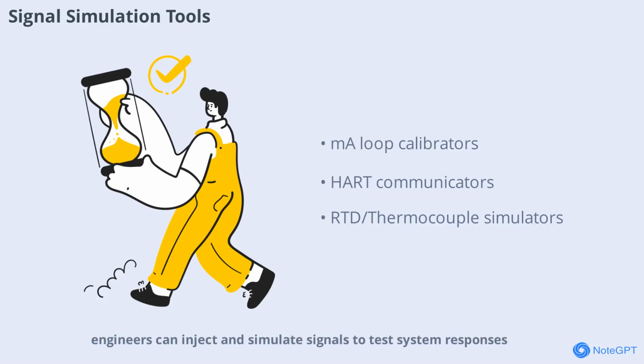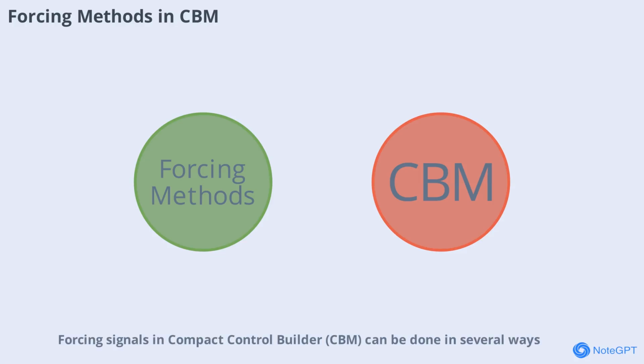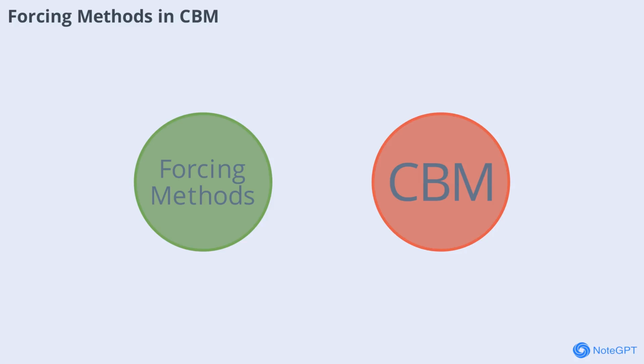Using these tools, engineers can inject and simulate signals to test system responses, ensuring that all hardware and software components interact correctly. Forcing signals in Compact Control Builder (CBM) can be done in several ways: via the watch window, directly on the FBD logic sheet, or at the hardware I/O level. Forces survive a warm restart of the PLC but are cleared during a cold restart. Understanding these methods is crucial for effective commissioning and troubleshooting, allowing engineers to simulate and test system behavior under controlled conditions.